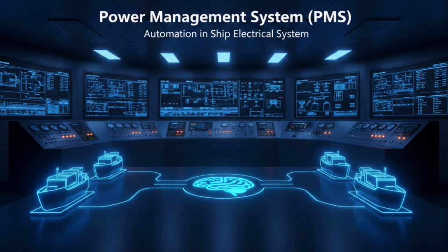Imagine a scenario where multiple generators are running, cargo pumps start suddenly, and the load rises sharply. Without PMS, overload trips could occur, causing blackouts. With PMS, the system automatically starts standby generators, balances the load, and ensures critical equipment like steering gear and navigation lights remain operational.